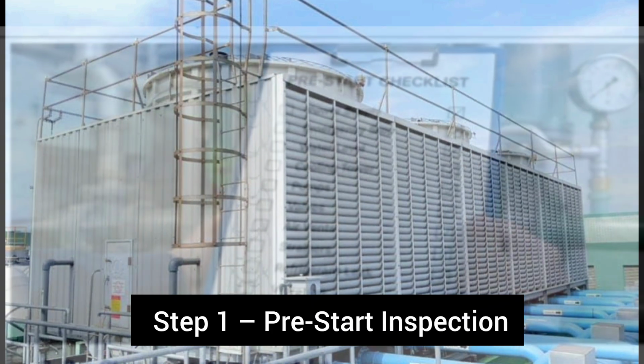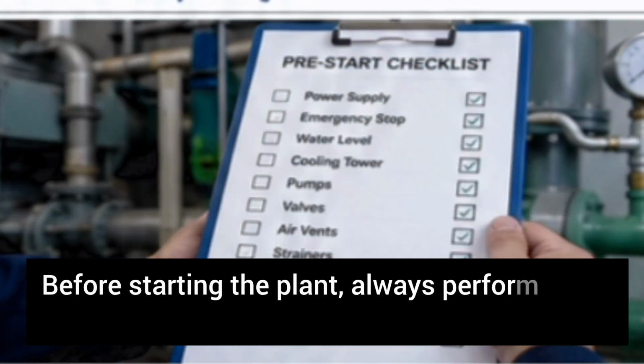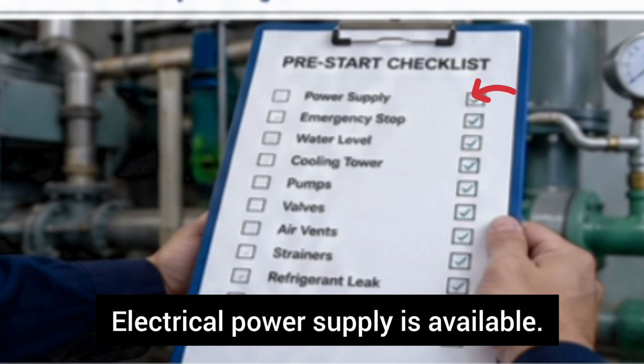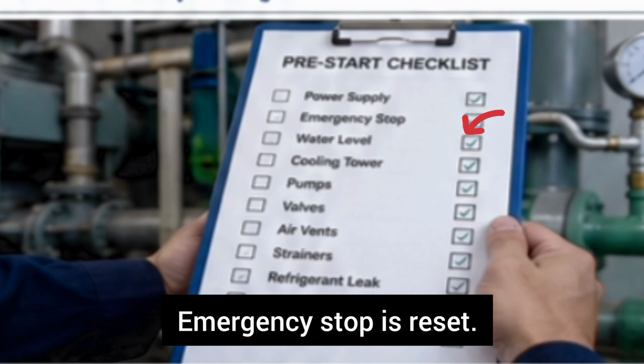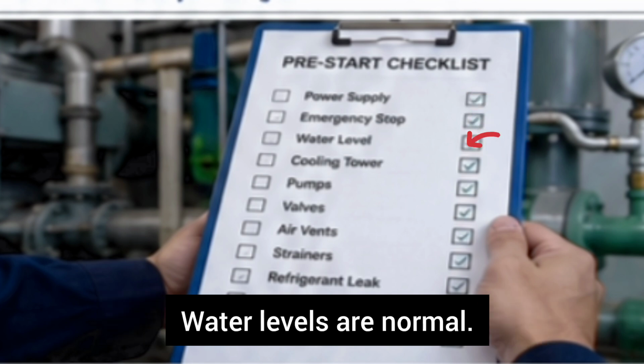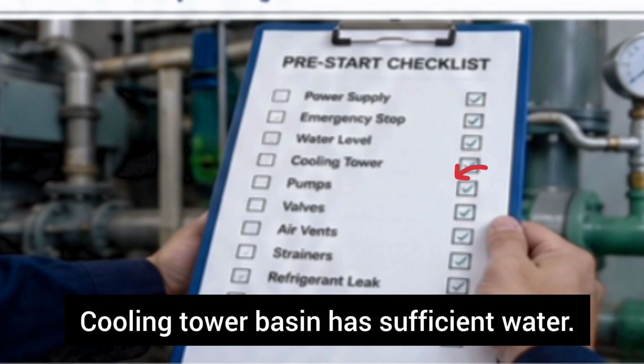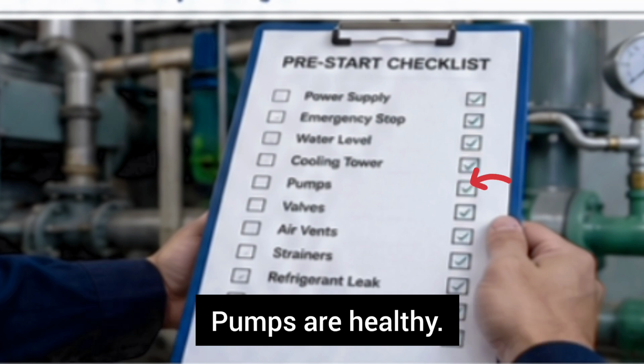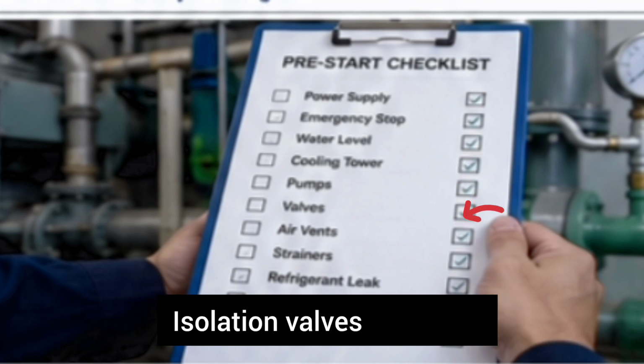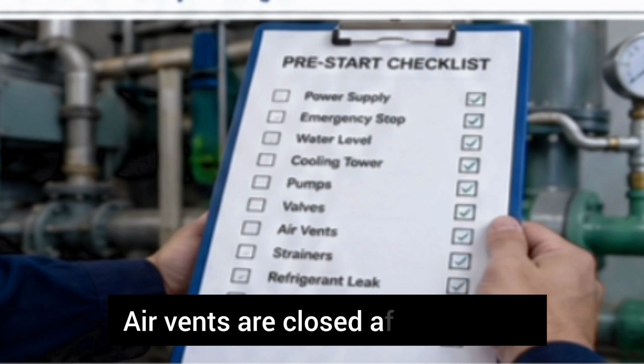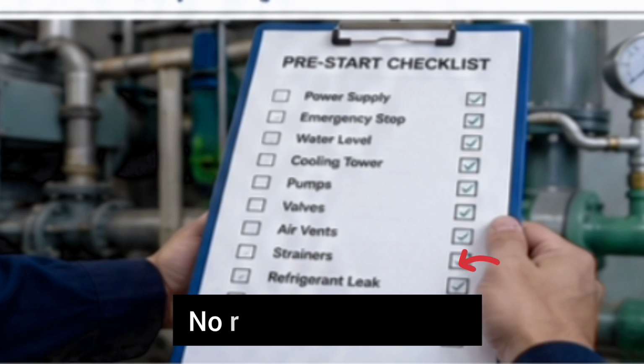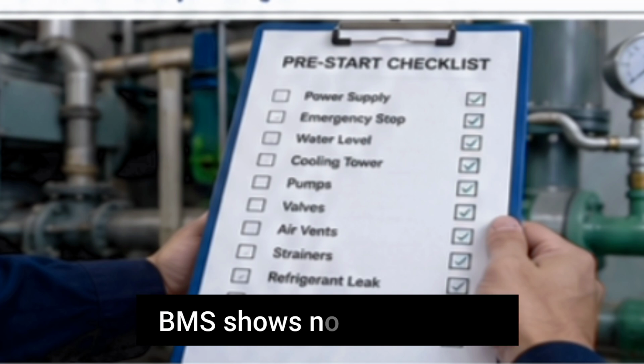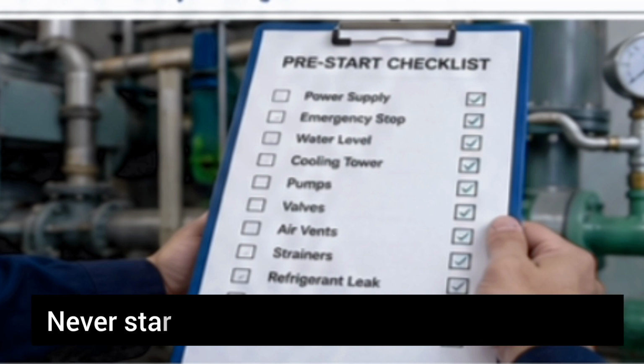Step 1. Pre-start inspection. Before starting the plant, always perform these checks. Electrical power supply is available. Emergency stop is reset. Water levels are normal. Cooling tower basin has sufficient water. Pumps are healthy. Isolation valves are open. Air vents are closed after venting. Strainers are clean. No refrigerant leakage. No abnormal vibration. BMS shows no active alarm. Never start a chiller without proper water flow.